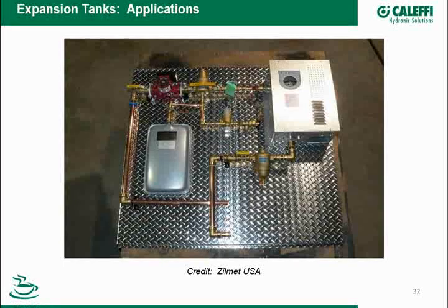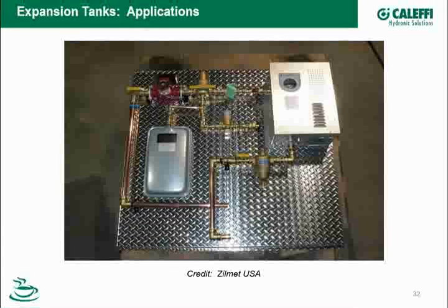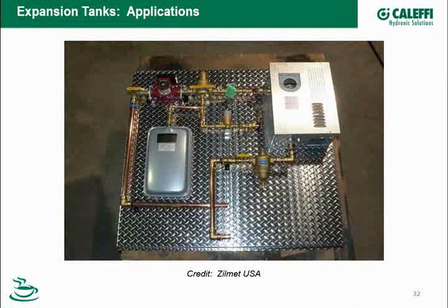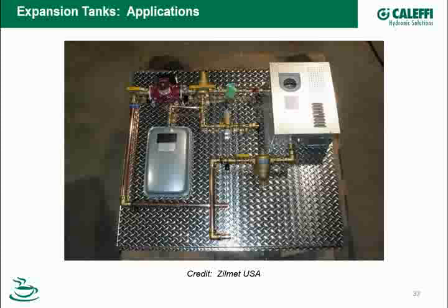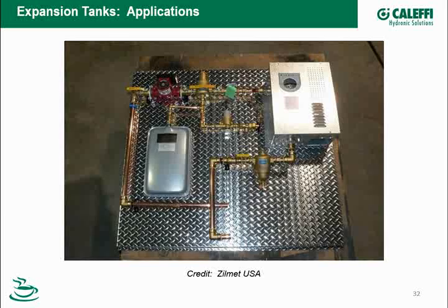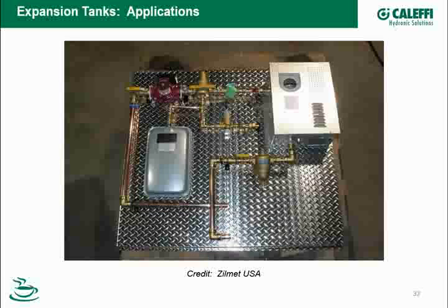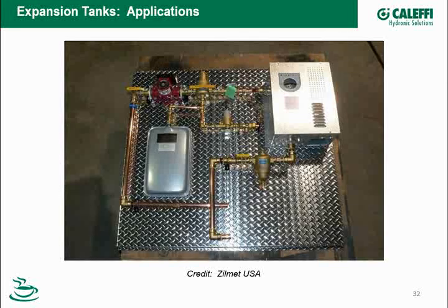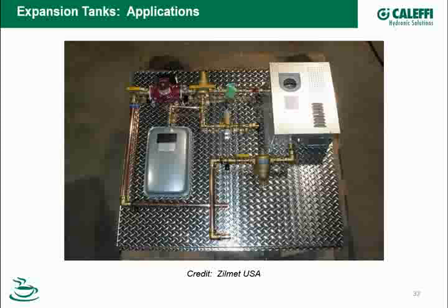Questions about insulation? Yes, a quick question. Can a small expansion tank be installed above the pipe, and will the diaphragm eventually fill with air and decrease the acceptance capacity of that expansion tank? The question is, can the expansion tank... Mark, everybody hears the question, correct? Yes. Okay. Yeah, question is, you're talking about putting an expansion tank above the pipe and placing it upside down.